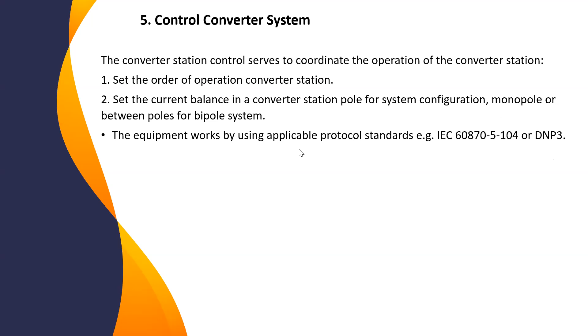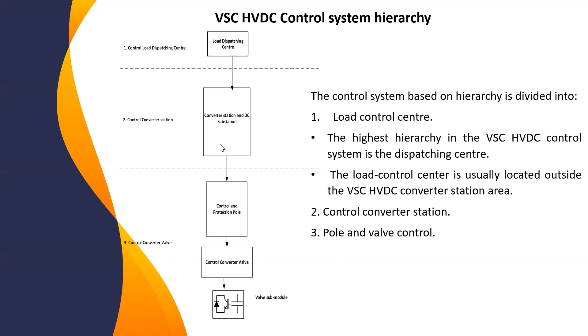And then when we are talking about control, we are talking about hierarchy. The highest hierarchy will be the load dispatching center. Usually the load dispatching center is not in the converter station, maybe a bit far, but depending on the site. Sometimes it can be close, but most of the time quite far. And then we also have a control converter station here. And then the last one, we have control converter valve. So this is the example. This is once again a typical hierarchy of control station in VSC.